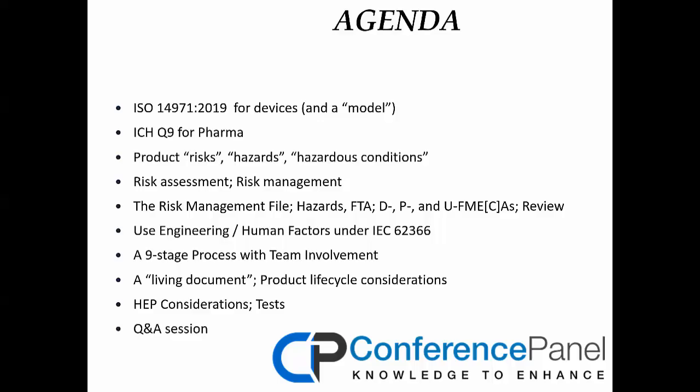We'll spend a little less time on that, or human factors engineering under IEC 62366. Now, there are a lot of standards and guidance out on human factors, and they deal with specific issues, and they are not excluded. They are included in this under tests. But IEC 62366 deals with a process of usability engineering. So we'll focus on the process, which should be used whether you're dealing with a system in the United States or in Europe or Asia or elsewhere.